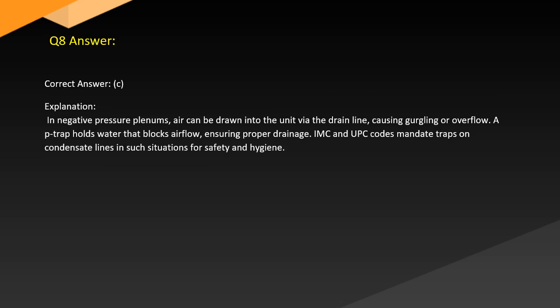Answer. Correct answer: C. Explanation: In negative pressure plenums, air can be drawn into the unit via the drain line, causing gurgling or overflow. A P-trap holds water that blocks airflow, ensuring proper drainage. IMC and UPC codes mandate traps on condensate lines in such situations for safety and hygiene.